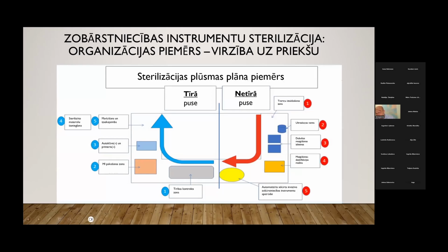For the reprocessing of dental instruments, like in a CSSD, like in a sterilization unit, moving forward is important, from the dirty to the clean, with the different steps, and we avoid going into the clean area with dirty clothes. I mean, you all know this point, but it's quite important, and it makes sense.